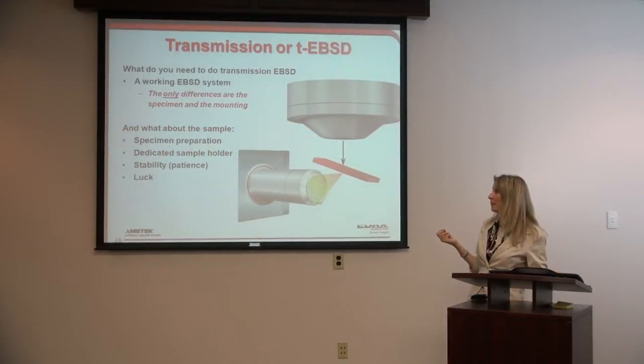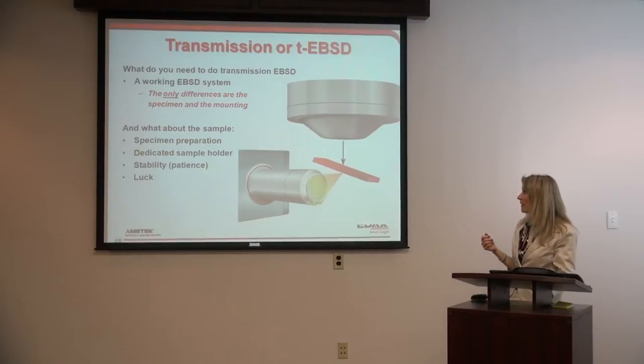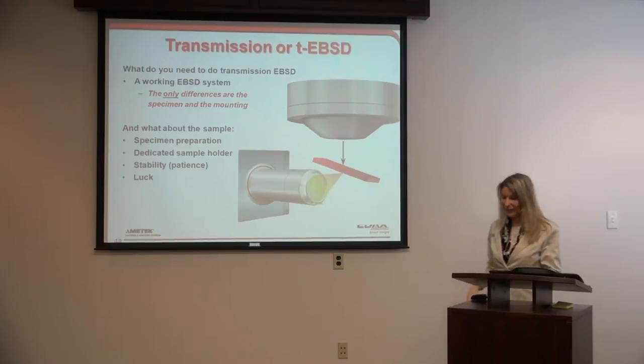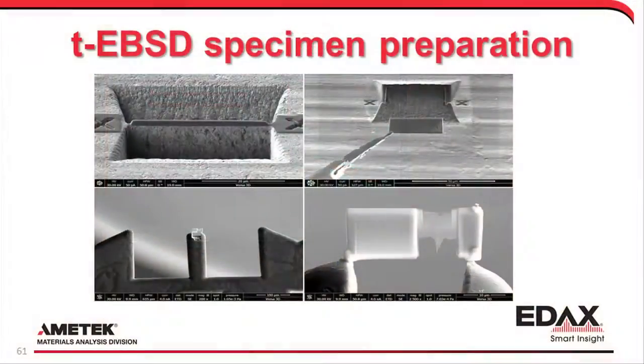We need a thin sample, we need a sample holder, and just a little bit of extra time and sometimes luck getting our patterns through the material. And this is where it's a new technology. Sample prep is nowadays using the focused ion beam and lift out capability where we mill away a sample, dig out our sample if we will, and make it very thin by milling it away.